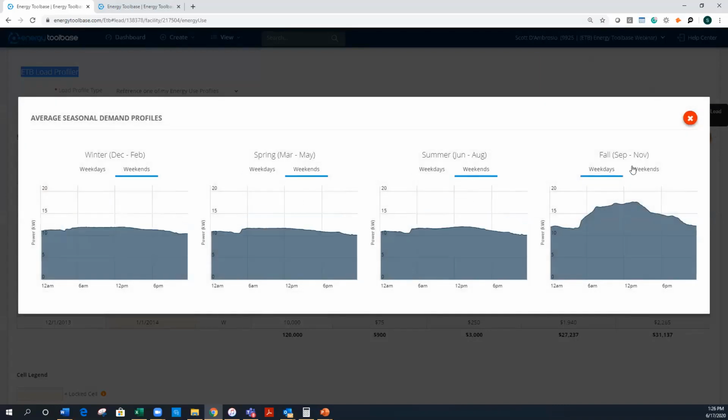When we think about peak demand shaving, well, this would be extremely hard to have economic value for peak demand shaving, right? Because if we said that you're trying to reduce the highest 15-minute increment pull, well, batteries only have a certain amount of capacity, right? These have almost 24-hour shoulders with a 2-hour battery. There's going to be no value for peak demand shaving here.